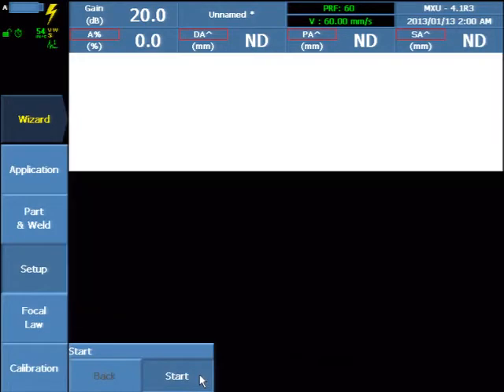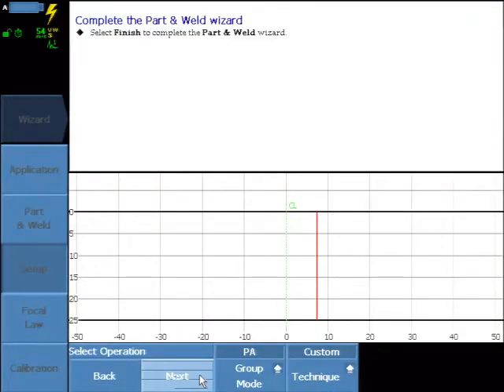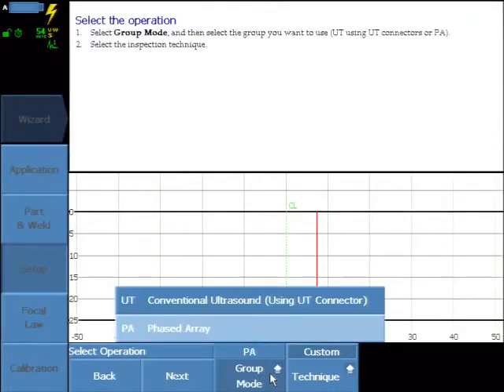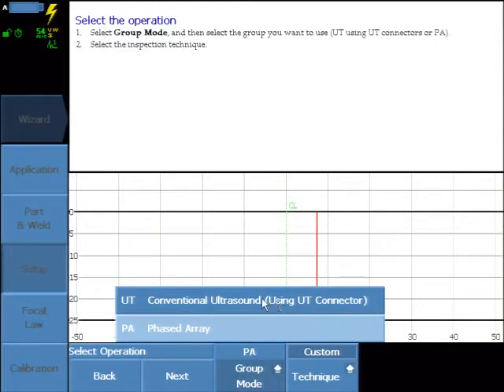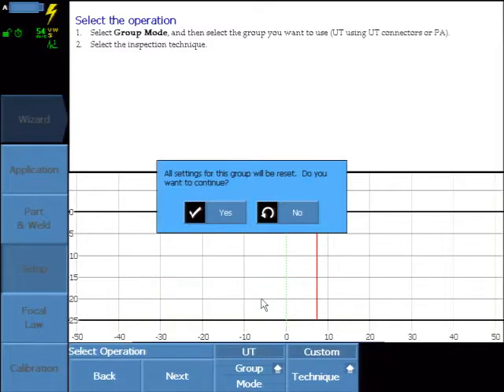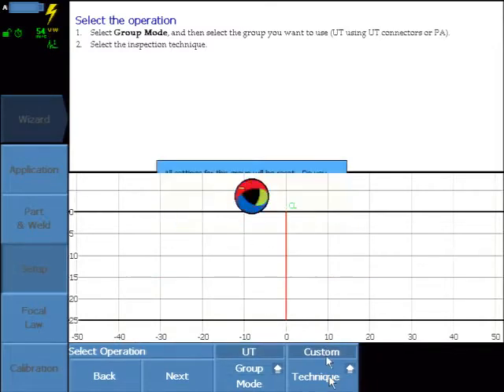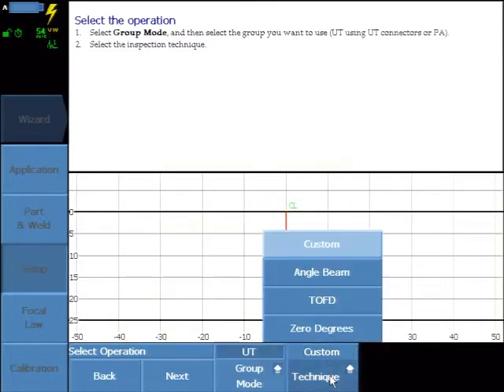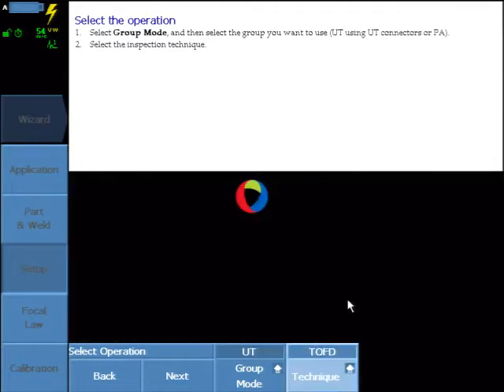Select Start. The OmniScan SX comes with a 64-element phased array connector and two conventional LEMO connectors. Select UT Conventional Ultrasound and Technique TOFD. This will shortcut our setup and load some system defaults relative to the TOFD inspection.